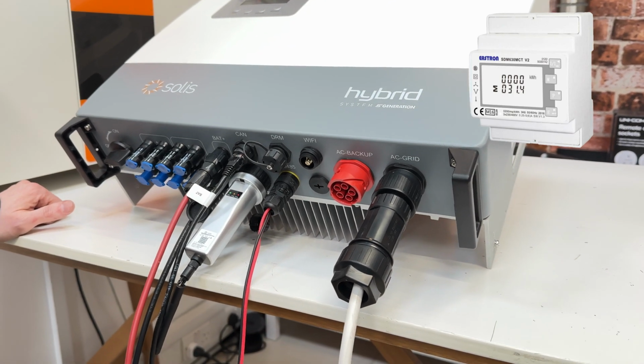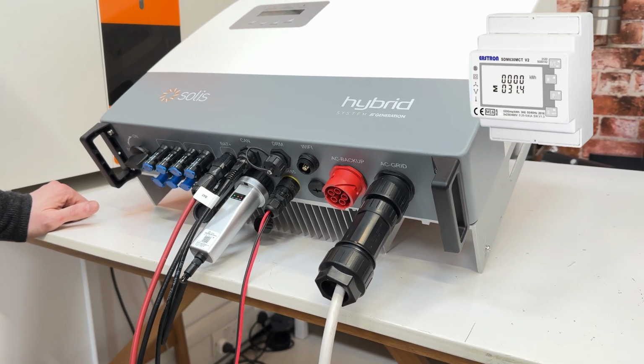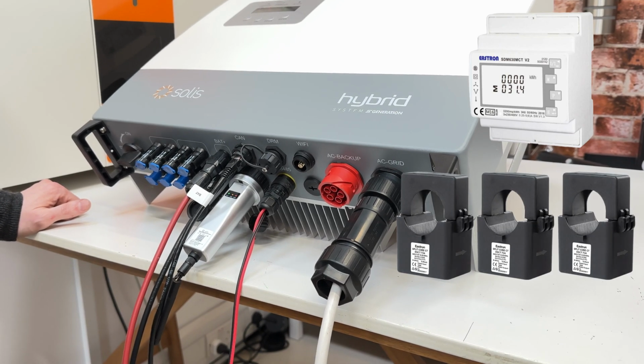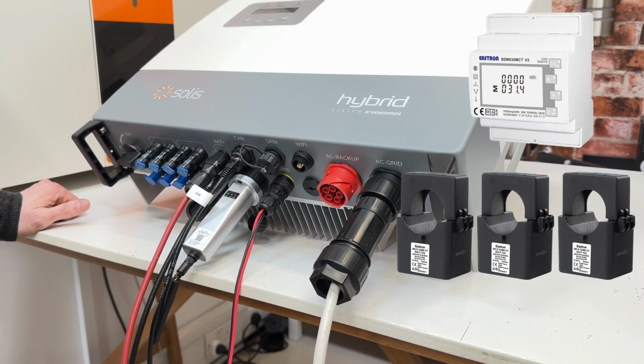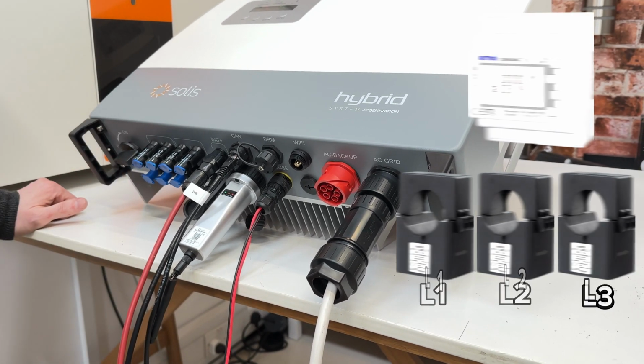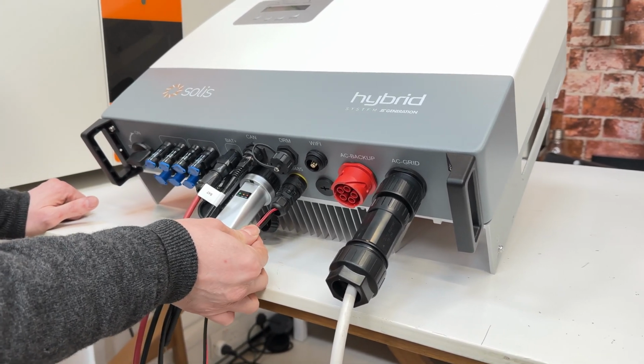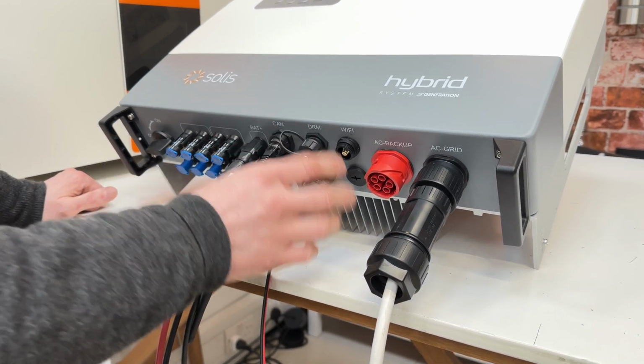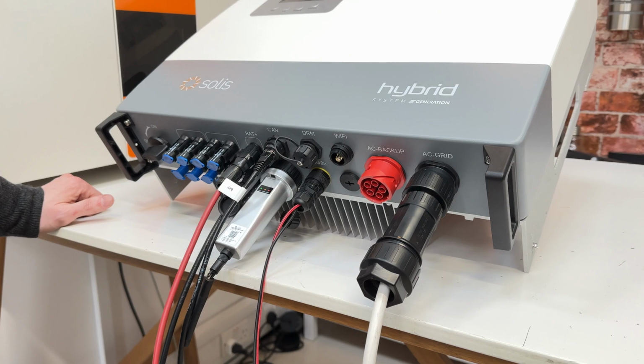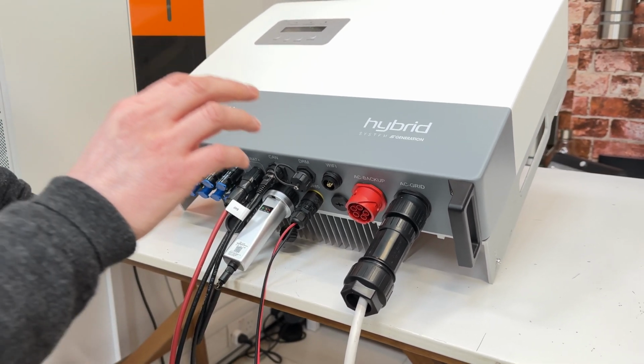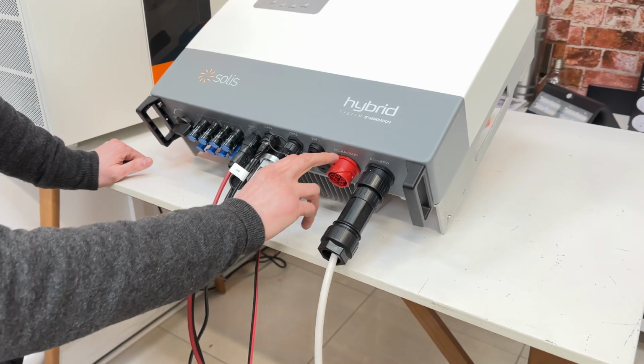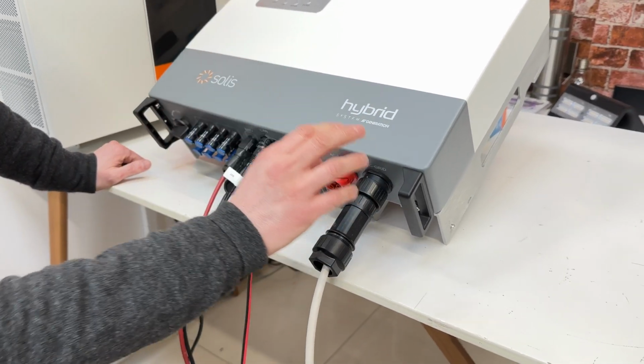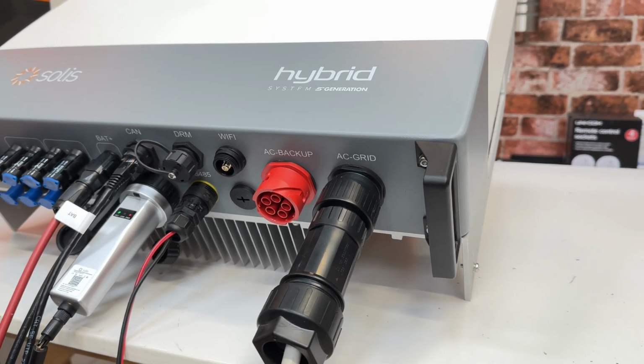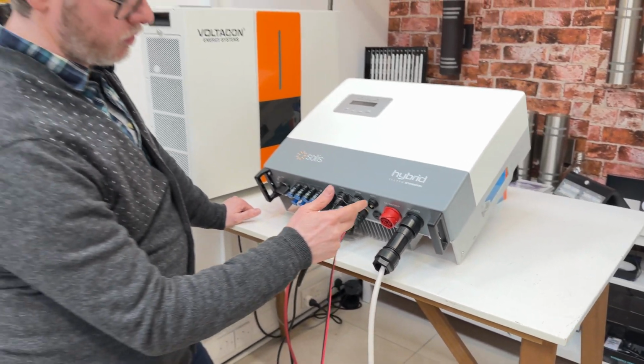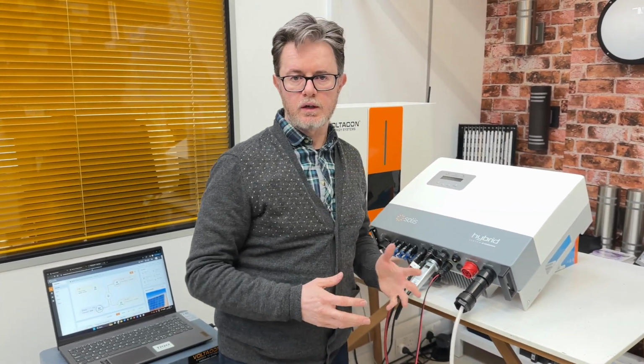You need to communicate with the energy meter that is connected at the incoming power supply of your property. And there are three external CT sensors on phases L1, L2, and L3. And the Modbus signal is connected here with two cables, positive and negative. So at any time, the inverter knows exactly how much energy your property requires. We don't use off-grid at the moment, so this socket is free. We are connected to the grid with a five-core cable, L1, L2, L3, neutral and ground.